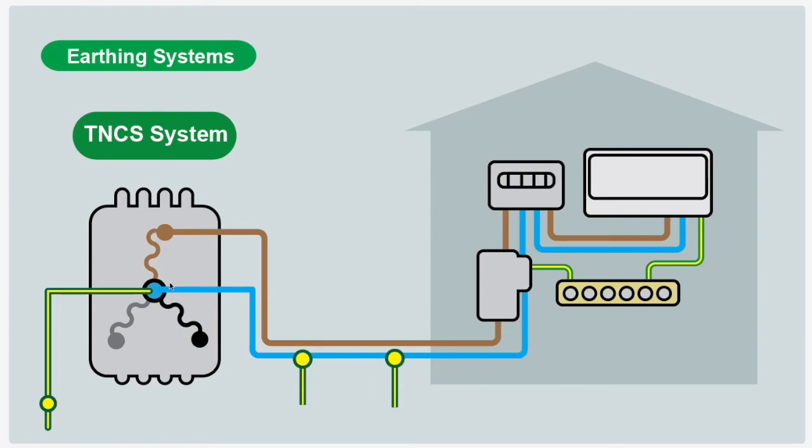The neutral is combined back at the star point of the transformer to earth as a reference to earth. So they thought they might as well use the neutral as the earth return path into the property. The earth comes along the neutral, it's combined with the neutral external to the property, and internal to the property it's separated.